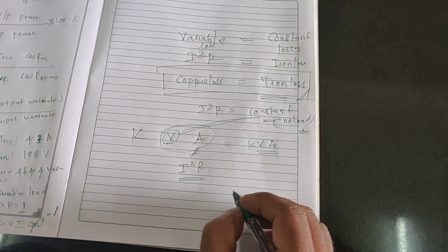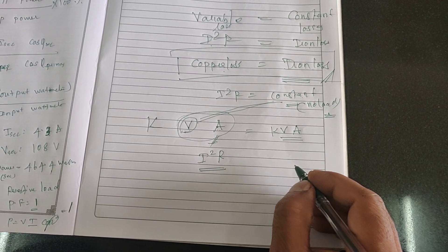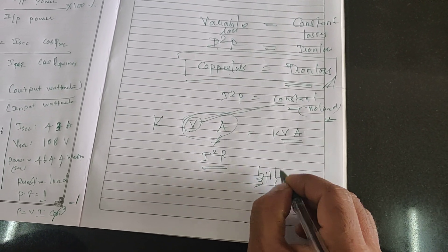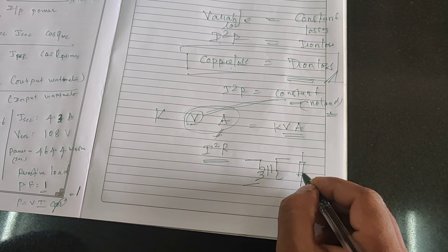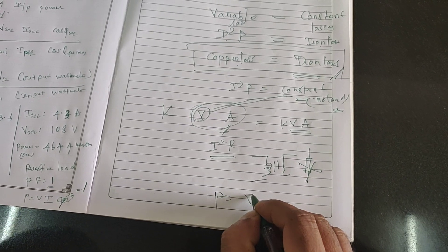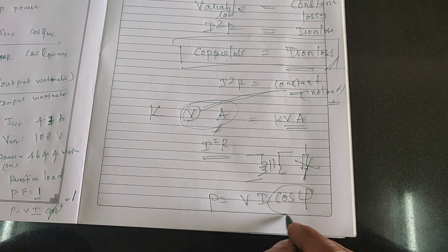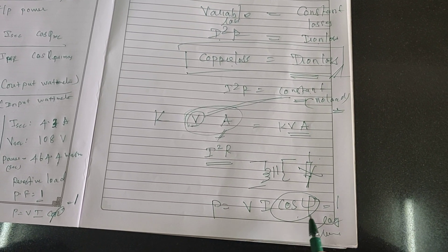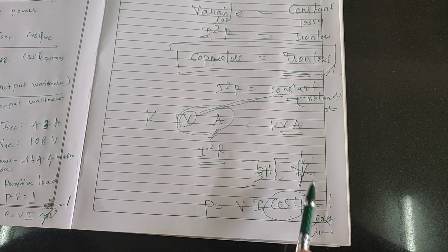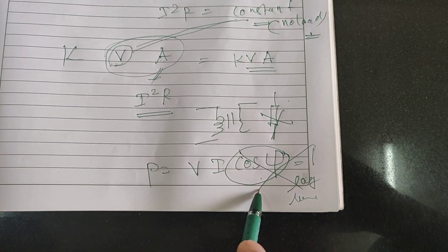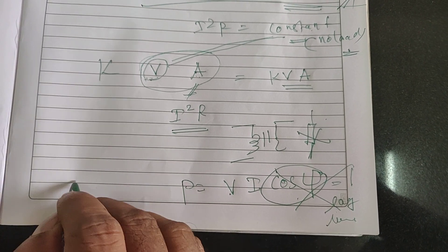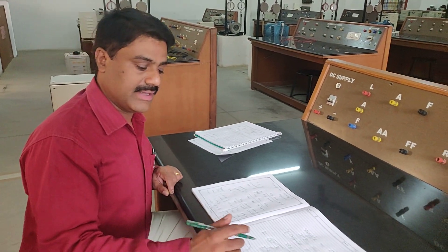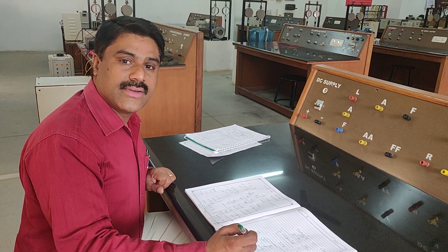On the other side, colloquially speaking, at the manufacturer's end, the transformer does not know what type of load it is going to supply. The manufacturer does not know the load information — load information is not known. Therefore, the power P = V × I × cos θ, and this cos θ is not known at the manufacturing side. It may be unity, lagging, or leading, depending upon the load connected to the transformer. Therefore, it is rated in V and I — that is, kVA. I hope I answered why a transformer is rated in kVA.